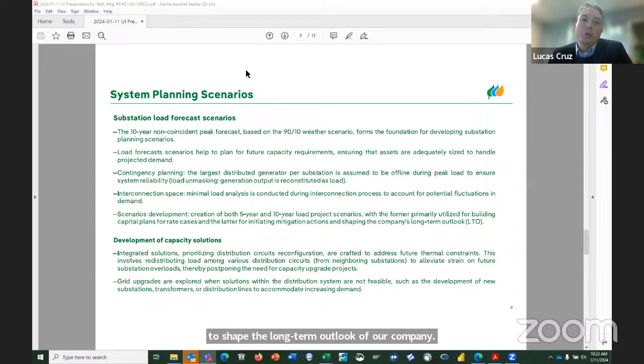With the scenarios developed, we identify the specific year each need is expected to occur, and then we start development of the solutions or projects. We prioritize solutions at the distribution system level, which usually have lower costs and are more efficient. We seek, for example, circuit reconfiguration, load transfer among neighboring circuits and substations, and creation of new circuit ties to increase the number of alternative solutions. Then grid upgrades such as substation capacity increase, new distribution feeders, new substations are explored only when solutions within the distribution system are not feasible.